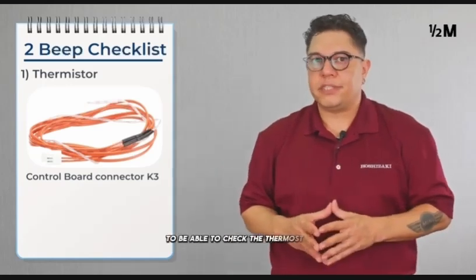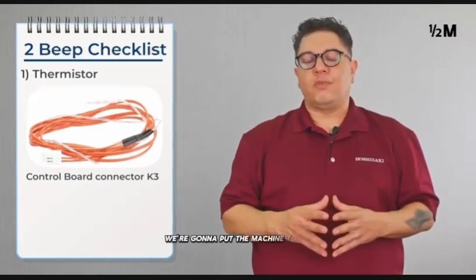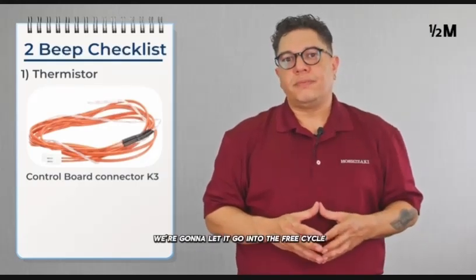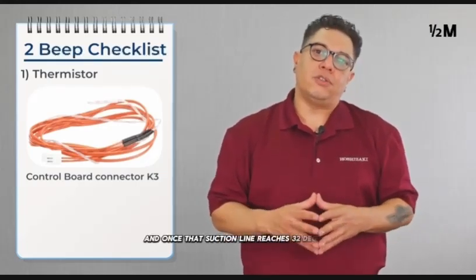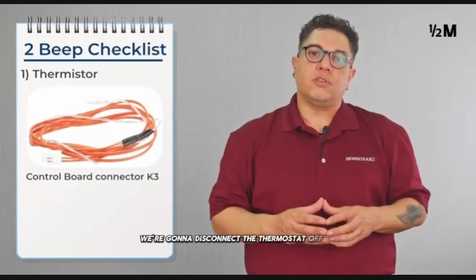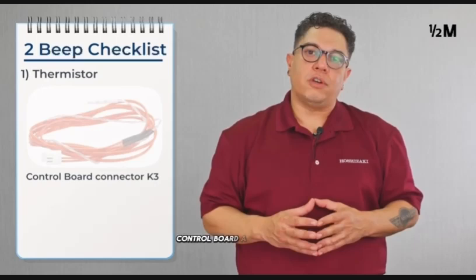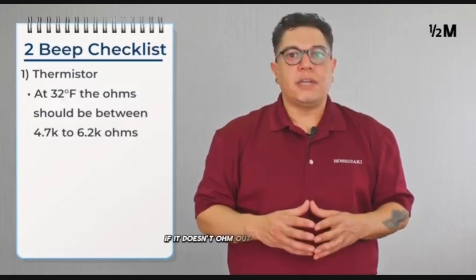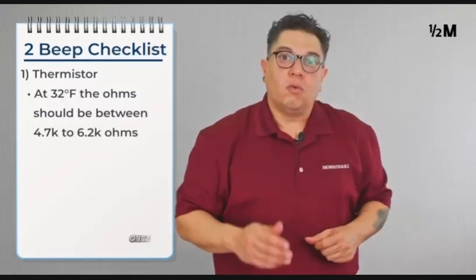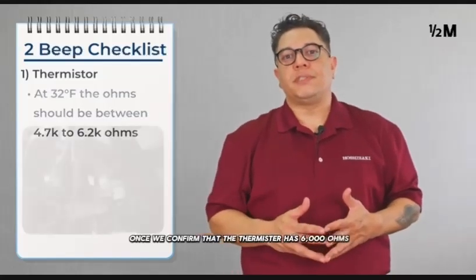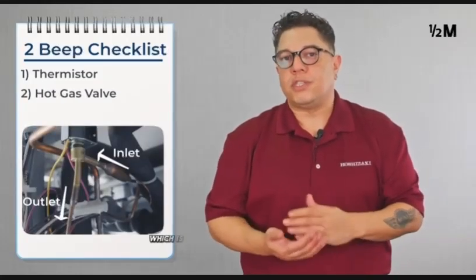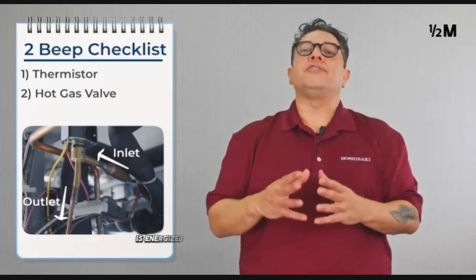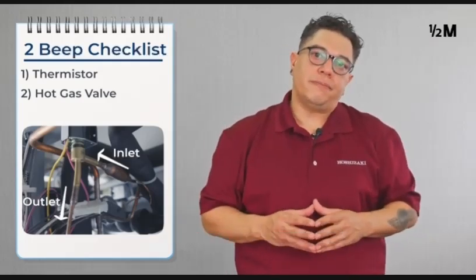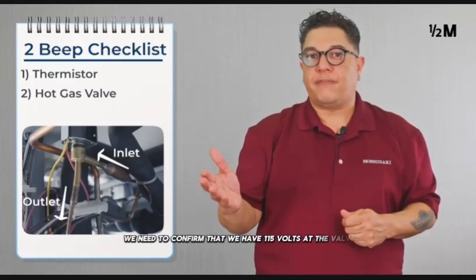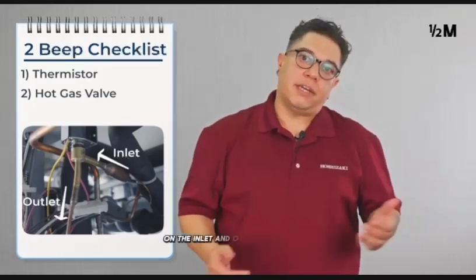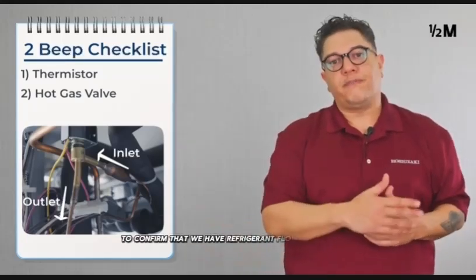To be able to check this thermistor, we're going to put the machine to run. We're going to let it go into the freeze cycle, and once that suction line reaches 32 degrees, we're going to disconnect the thermistor off the control board and ohm it out. It should ohm out to 6,000 ohms. If it doesn't ohm out to 6,000 ohms, we're replacing the thermistor. Once we confirm that the thermistor has 6,000 ohms, then we can move on to the next step, which is confirming that the hot gas valve is energized and refrigerant is flowing through it. We need to confirm that we have 115 volts at the valve, and then we're going to take temperatures on the inlet and outlet of the valve to confirm that we have refrigerant flowing through it.